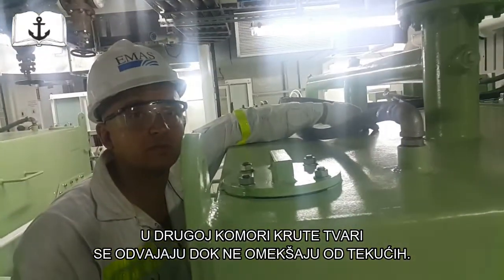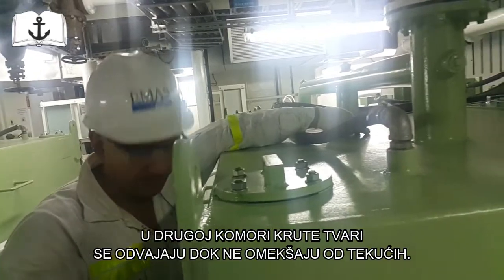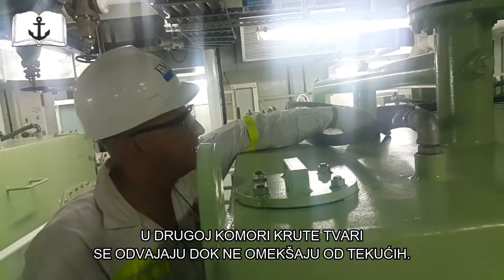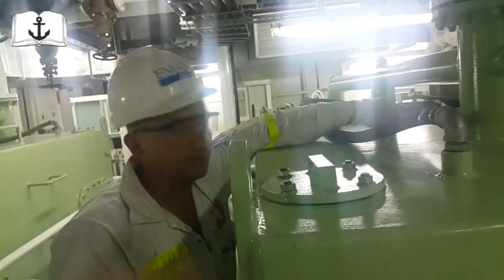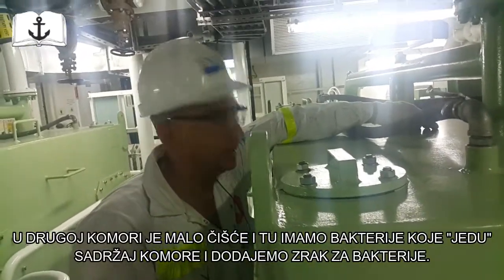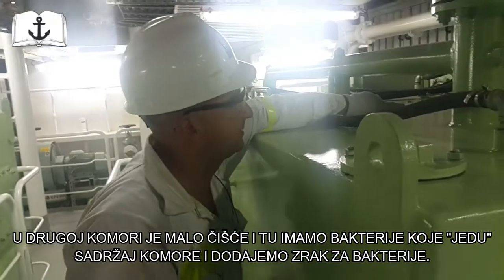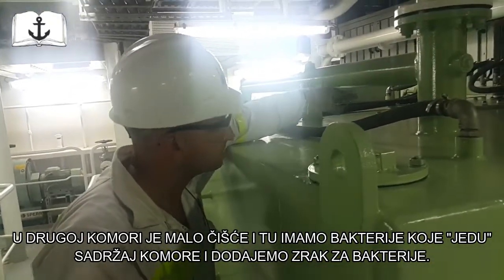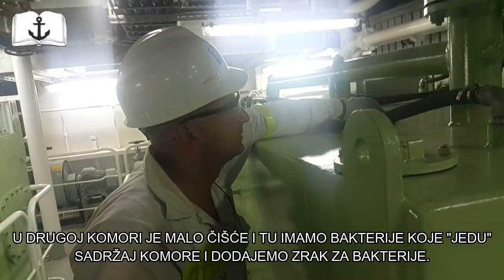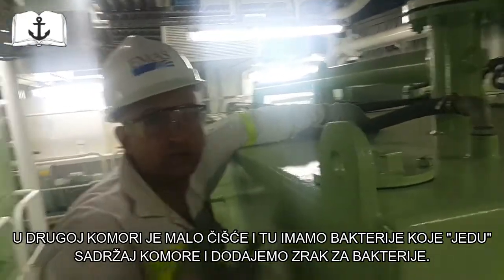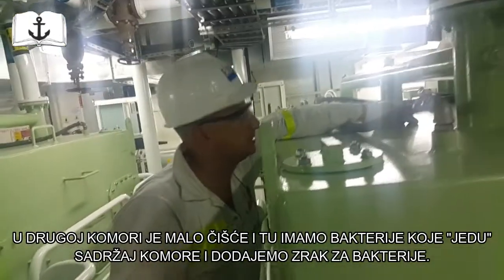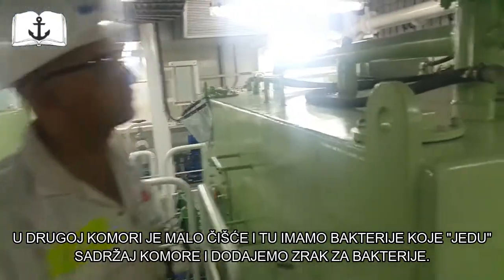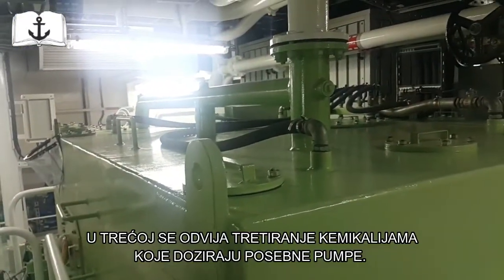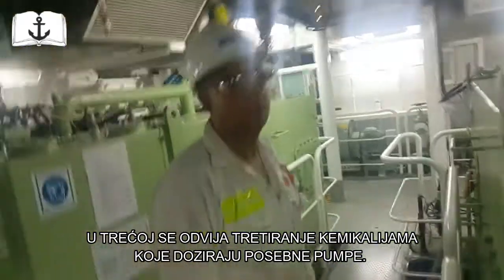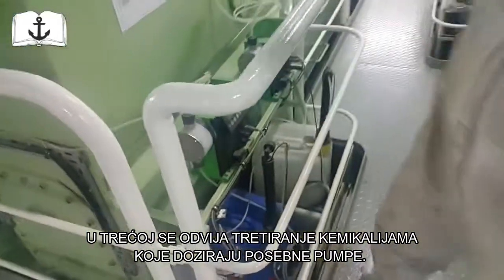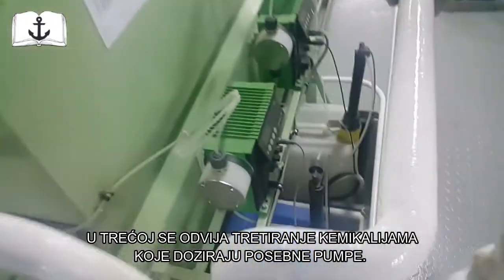So the hard stuff is left in the first one, right? Yes, but it's waiting to become softer. Yeah, okay. And then when it goes to the second one, it's already a bit cleaner, right? Yes. Where do you have bacteria? In the second chamber. In the second chamber you have bacteria which are eating all the waste, basically, right? Yeah. Okay. You need the air to give energy to the bacteria, and you are giving air to the bacteria so they can live. Okay. And the third one is a chemical treatment. And in the third one you put chemicals inside. Yeah. Like that. And it's dosed by the pump. This is a dosing pump or something?